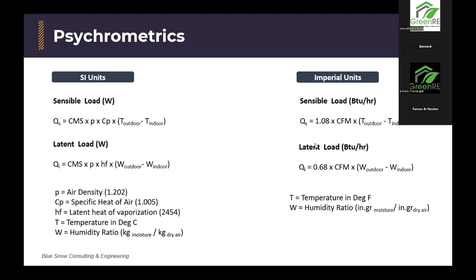It is also very important to decouple this in some of the specialized designs you're going to see. For example, if you're going to use an active chilled beam or a radiant cooling system, those systems are very good and very energy efficient at handling sensible load. But your latent load, you'll need to decouple it, take it aside, and put it into another system, which is called the DOAS. So that is more on load balancing. You'll need to do those kinds of things.